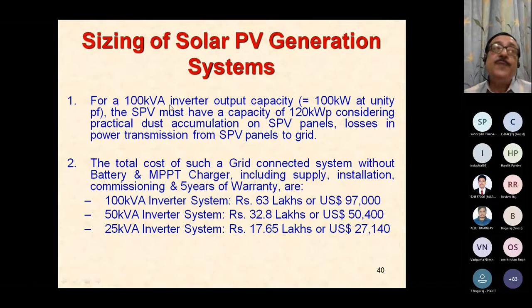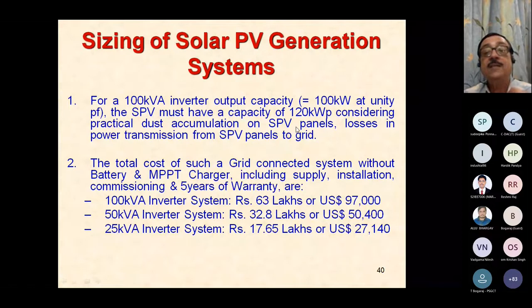It's like when you buy a UPS, you see there are lots of tricks. Suppose you are buying a 100 watt system, they'll say no, you can't load it up to 100 watts, you can load it up to 80 watts. Those are commercial aspects, not technical aspects. Technically, a 100 kVA inverter should be able to provide you 100 kilowatts of power at unity power factor. The current is the limiting factor. If your power factor becomes less than unity, then of course the available wattage will reduce because you will hit the current limit. And then the solar photovoltaic panel must have a capacity of typically 120 kilowatts peak. Considering the practical dust accumulation on the panels and the losses in power transmission from the panels to the grid, everything combined, you have a roughly 120 kilowatt peak capacity requirement for a 100 kVA inverter system.